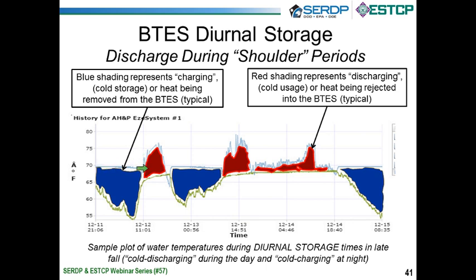Before, the blue line was the outlet water. Now it's the inlet water. So now we're dumping heat in. We didn't get any hotter than about 72 degrees and back down again, and now we flip again. So the dark blue represents the thermal cold storage we did that night. The red represents the amount we harvested during the day. Blue, back to storage again.